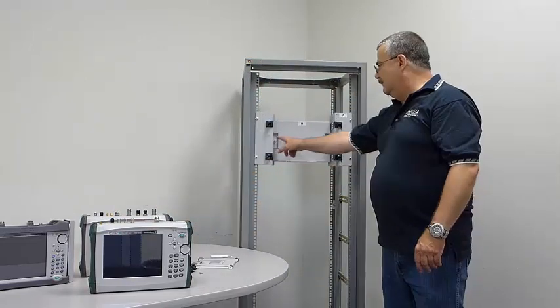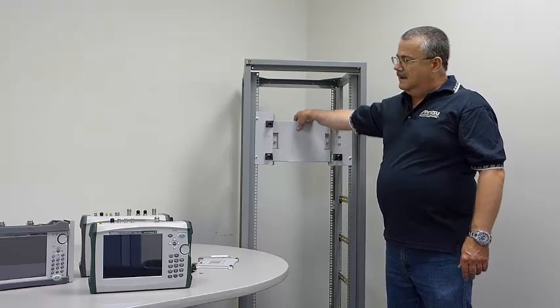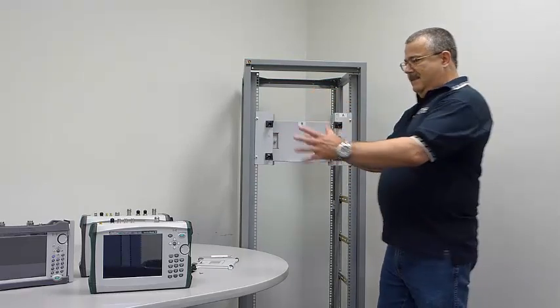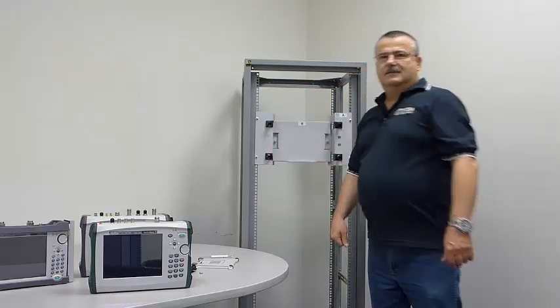You would remove this handle, just as we did on this. But you will also additionally remove the B spacer by taking these two thumb screws out and lifting this B spacer out. Then the larger instrument slides straight in and latches in place just as we did.